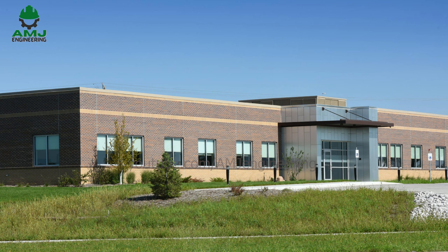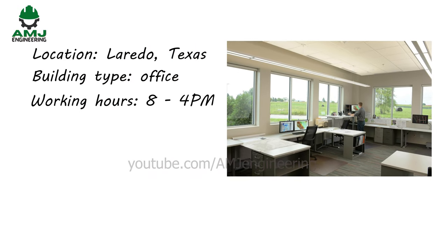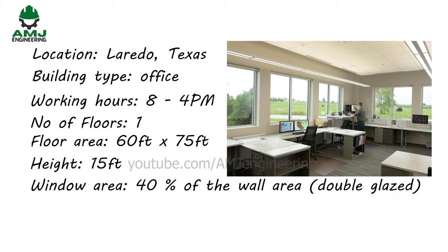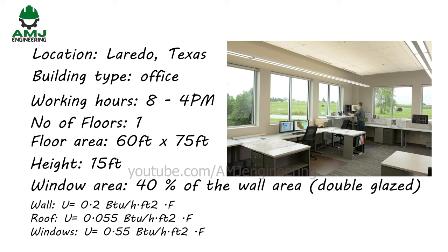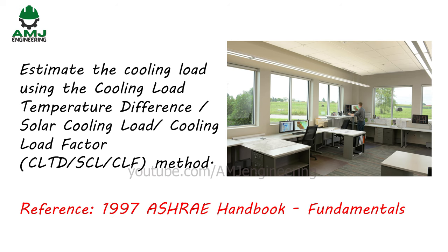Let us take this example. An office building in Laredo, Texas requires air conditioning for a single-story building. The following data is gathered: location Laredo, Texas; building type: office; working hours 8 a.m. to 4 p.m.; number of floors: 1; area: 60 feet by 75 feet; floor-to-floor height: 15 feet; window area considered 40% of the wall area; windows are double-glazed. We will estimate the cooling load using the CLTD-SCL-CLF method.